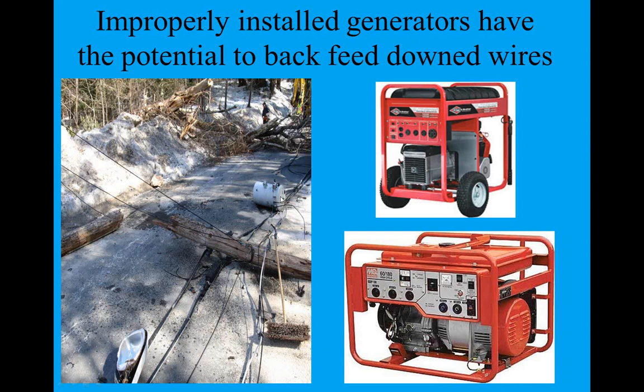They could inadvertently cause that transformer, which is supposed to step the primary down to secondary, to step the secondary up, and they're creating primary voltage down the primary line that's been dead in the street the last 4 or 5 days. And if somebody's walking down the street and the kids are playing or riding a bike, they're gone. They're history. They're toast. So that's why it's so critical that you use these generators safely and properly, and you've got a code-approved disconnect switch so you can't backfeed into the grid, because you can kill people with these things. And we find, unfortunately, more and more of these occurrences happening.